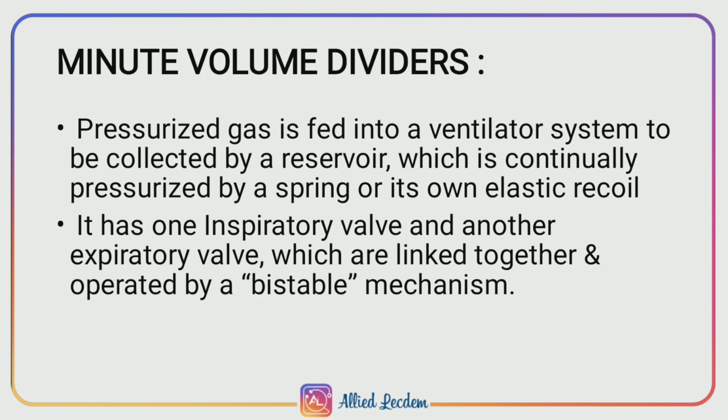Most minute volume dividers have an adjusting knob which varies the tidal volume. In this apparatus, we have one inspiratory and one expiratory valve linked together. These ventilators are referred to as minute volume dividers since they just divide up the intended minute volume supplied by the driving gas. Here, driving gas is nothing but pressurized O2 or air which is being supplied.